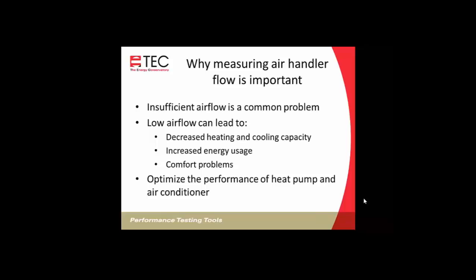And also being able to accurately measure airflow will allow you to optimize performance of your heat pump and air conditioner. You need to know what the airflow is. You need to set the airflow accurately before you set the charge on the system. So when you're setting up a new system, you need to accurately know what the airflow is.